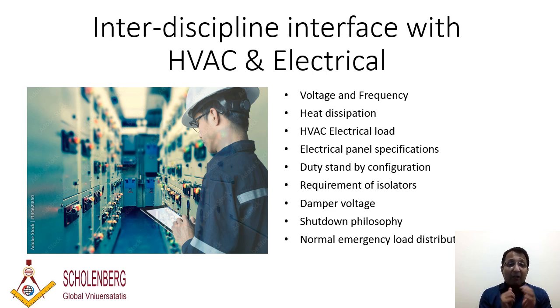Then there's the duty-standby configuration - one motor is duty, another is standby - and those inputs need to go to the electrical discipline. Then comes the requirement of isolators. You need to coordinate with electrical for maintenance purposes - isolators are needed at each major equipment so that if a fault happens, they can isolate it and do maintenance without any hazard or accident. It's good from a safety point of view too.